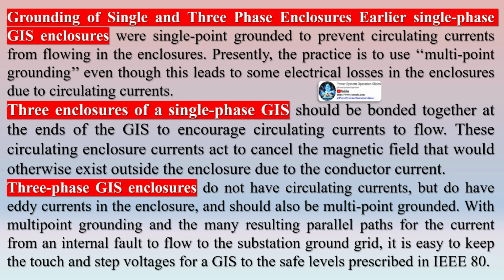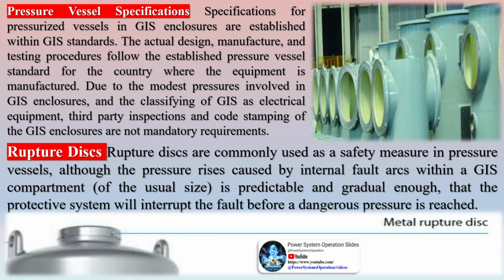3-phase GIS enclosures do not have circulating currents, but do have eddy currents in the enclosure, and should also be multi-point grounded. With multi-point grounding and the many resulting parallel paths for the current from an internal fault to flow to the substation ground grid, it is easy to keep the touch and step voltages for a GIS to the safe levels prescribed in IEEE 80.